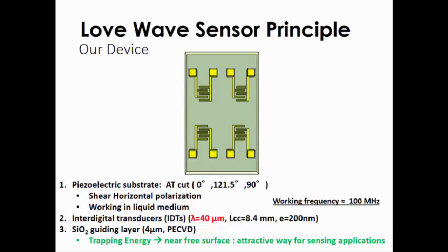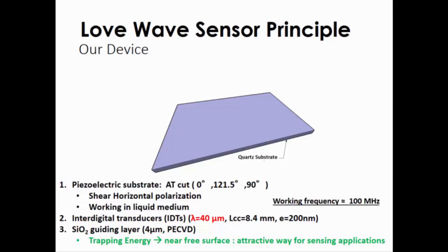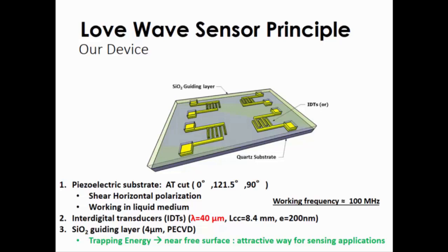Our device is presented here. It's a quartz substrate with an AT cut which allows us to have a shear horizontal polarization and to work in liquid medium. On this quartz substrate, we deposit an interdigital transducer in gold with a wavelength of 40 micrometers here and a distance here for the acoustic path near 8 millimeters, and the thickness of the IDTs is about 200 nanometers. After that, we deposit by PECVD a silicon dioxide guiding layer about 4 micrometers. The particularity of this kind of wave is that it's possible to trap the acoustic energy inside the guiding layer. By doing this, we will perturbate this energy close to the surface, to the free surface. Our working frequency is around 100 MHz.